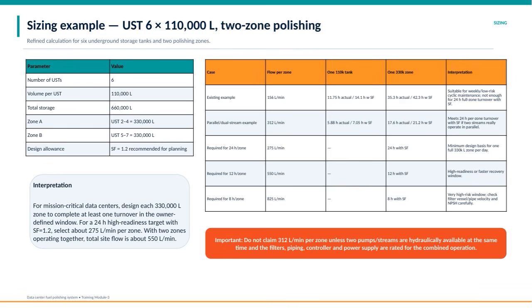For mission-critical data centers, the recommendation is to design each 330,000-liter zone to complete at least one turnover within the owner's specified window. Specifically, for a 24-hour high-readiness target with the safety factor of 1.2 applied, a flow rate of about 275 liters per minute per zone is advised. Operating both zones together would then yield a total site flow of approximately 550 liters per minute.